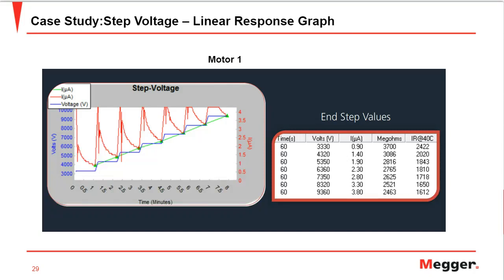As the step voltage rises, it measures the leakage current. Next step holds there for a minute, moves to the next step, and then we get a graph of the leakage current. And as it's clear to our naked eyes, it's a quite linear graph, which shows that the motor insulation is still in good condition.